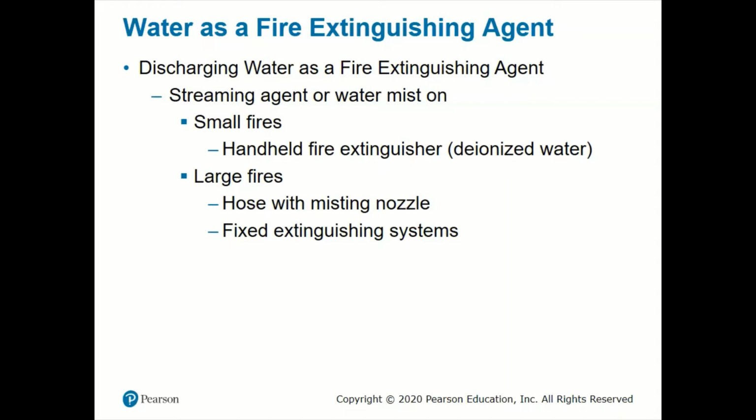So how can we use water? Well, it depends on what the circumstances are. There are small handheld fire extinguishers that use water as its fire extinguishing agent, either as just like a spray, just like a garden hose, or with a mister on it. And the advantage of the mister is it helps promote that vaporization. And that vaporization would allow the fire to actually be put out faster by taking more heat away more quickly.